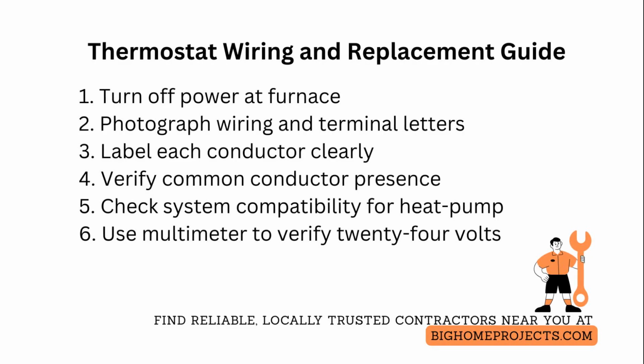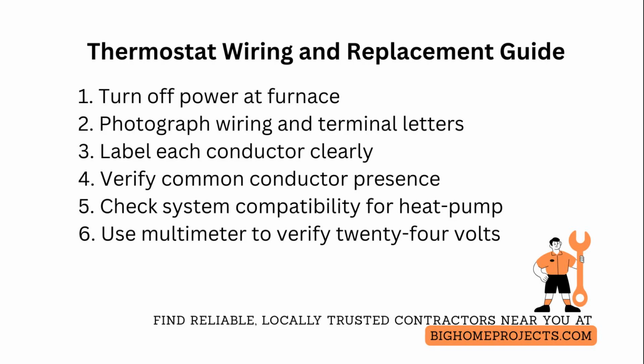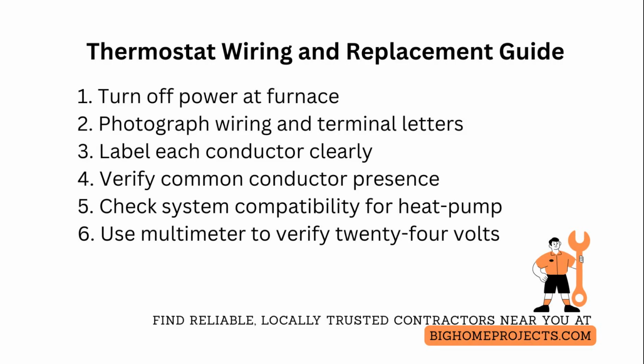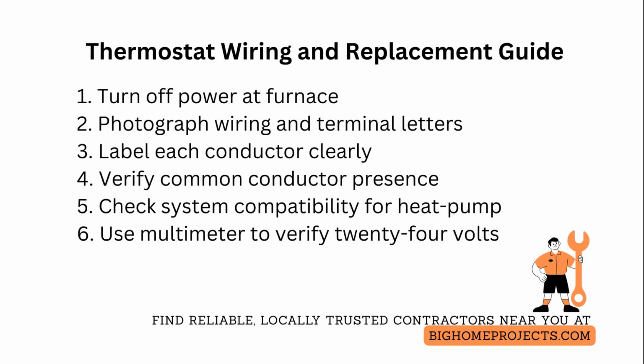Label each conductor so you never guess which wire goes where. And compare the terminal letters to the replacement thermostat's manual rather than assuming color to function mapping. Test for a common conductor by gently tugging the cable at the air handler and looking for a thicker bundle or a spare unused conductor.